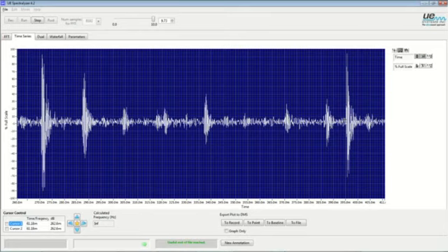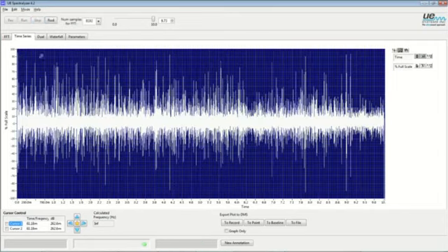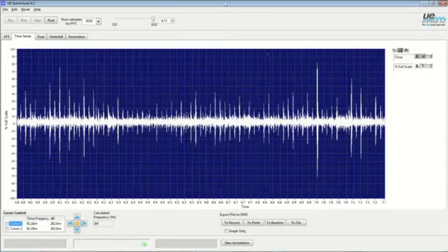It is not predictable like other events, and it can occur anywhere within that electrical sine wave. So this is an important consideration. It's the same type of fault, but with the different voltage system and the different type of measurement attachment, we still have the same signatures. Looking at the entire recording, there's our broad band of white noise. Here's our deviations from that center line indicating discharges of energy, and there are clearly differences in the spacing throughout the recording. That is your characteristic footprint of a tracking event.